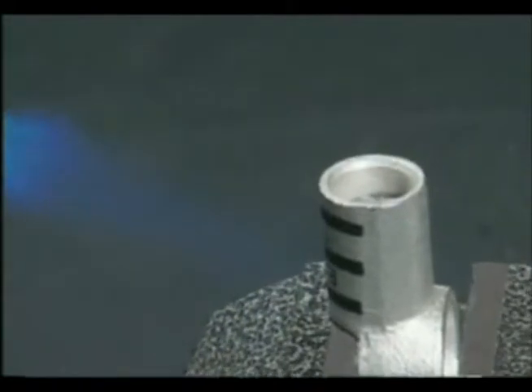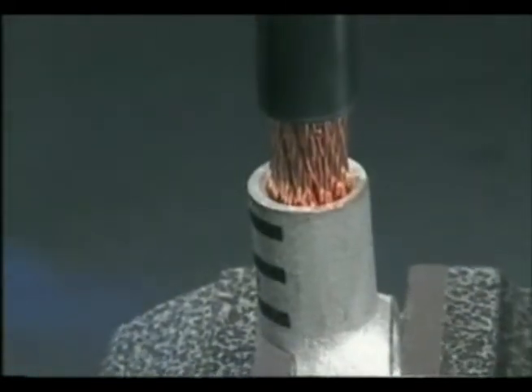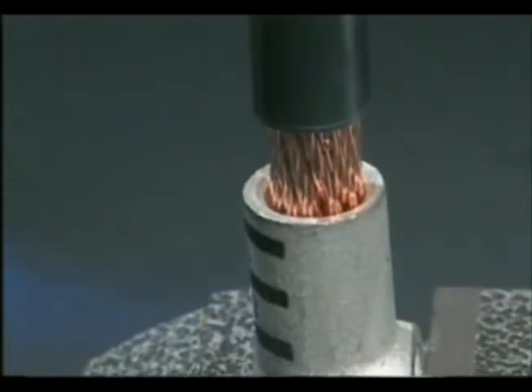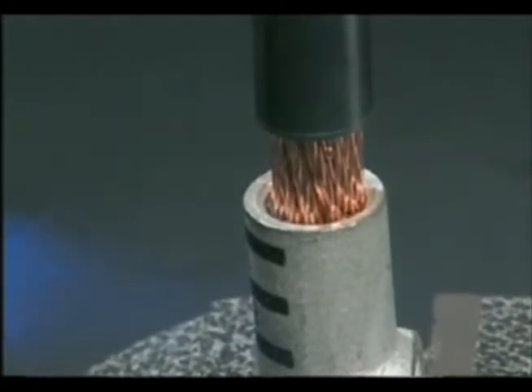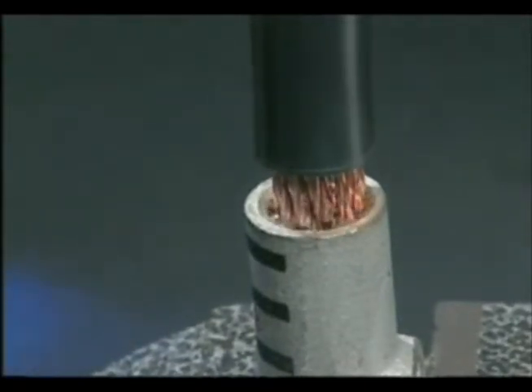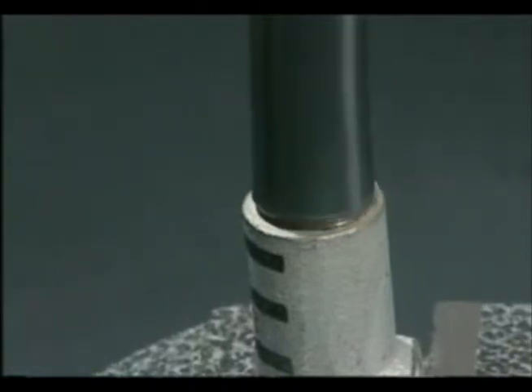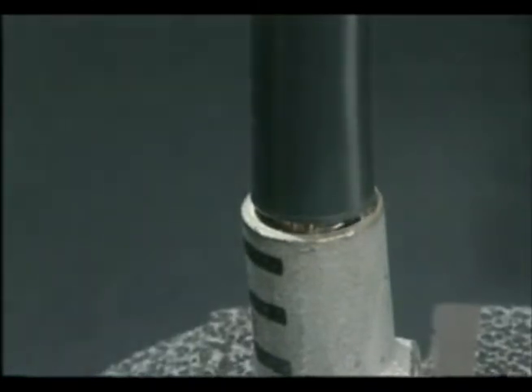Place the stripped portion of the cable into the terminal as the solder melts. Allow the exposed wire strands to sink into the terminal until the cable insulation is snug against the top of the terminal.